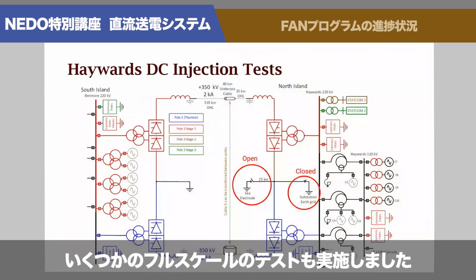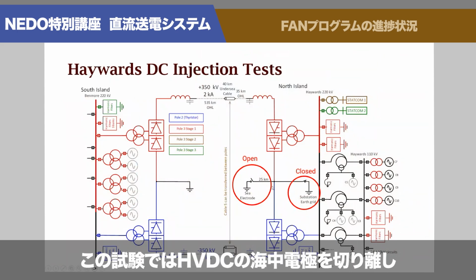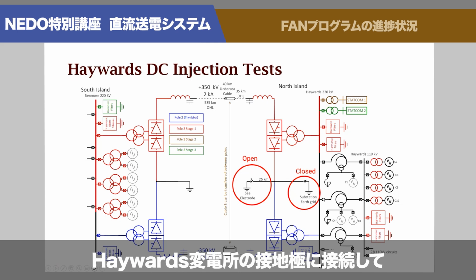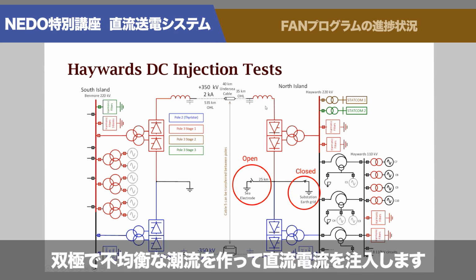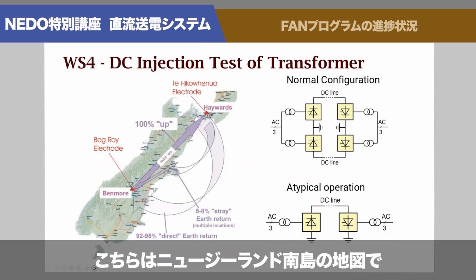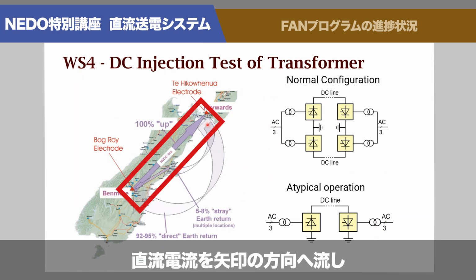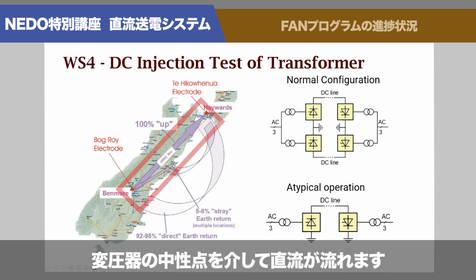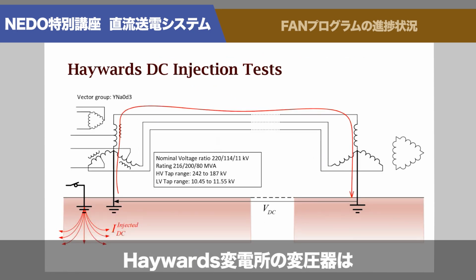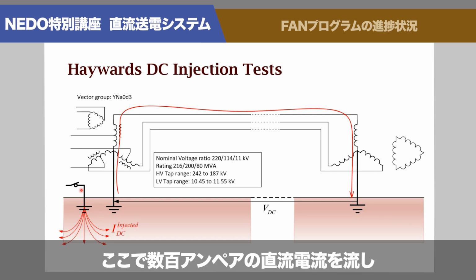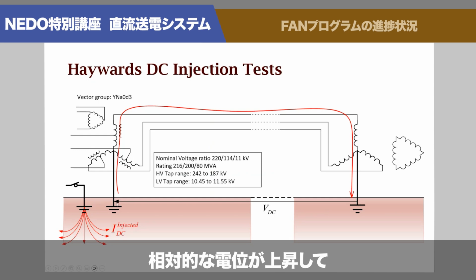We have done full-scale testing. What happened here is Transpower disconnected the electrode of the HVDC link, closed this one onto the earth grid at the substation Haywards, and operated the bipoles unbalanced, injecting a DC current. Here's Haywards, here's a map of the South Island, New Zealand, pushing DC currents from here to here with a bit of stray current through the neutrals of some transformers. So at the transformer at Haywards, we're pushing in DC current, a few hundred amps, and this raises the potential here relative to here, and you could get a DC flow.